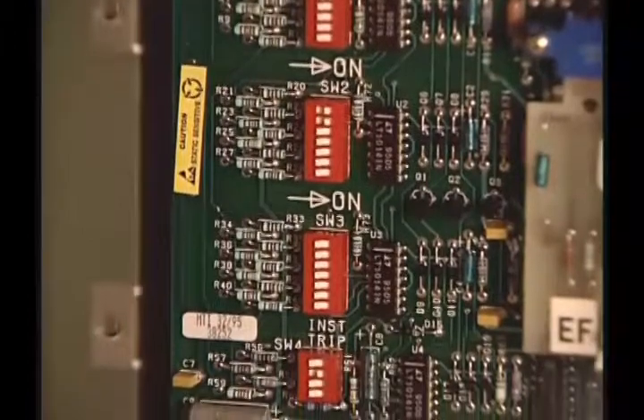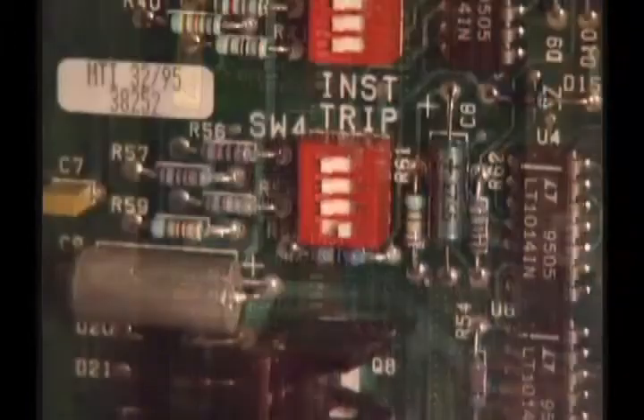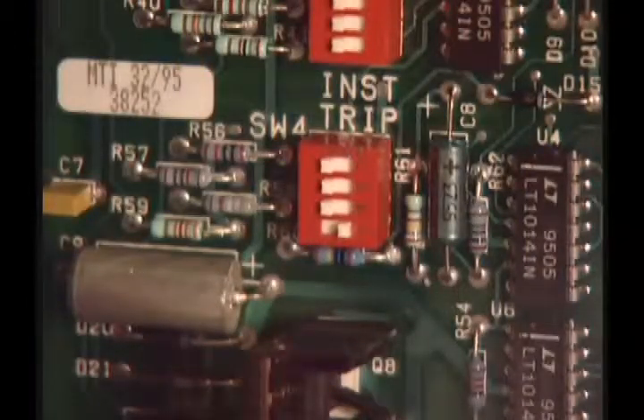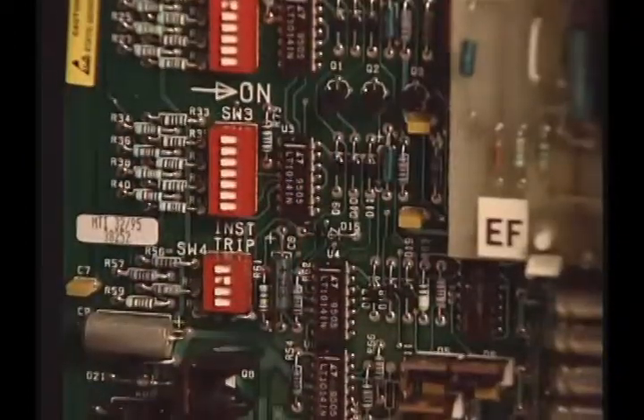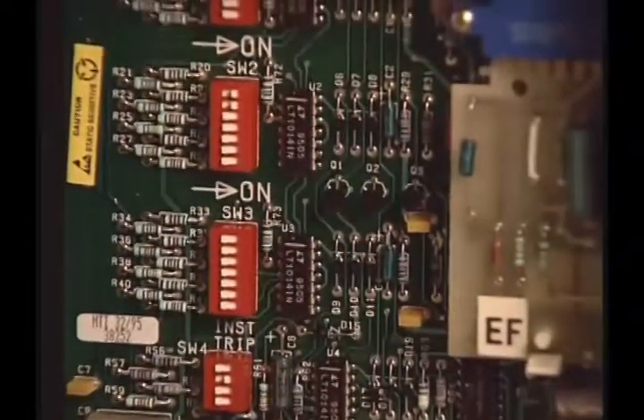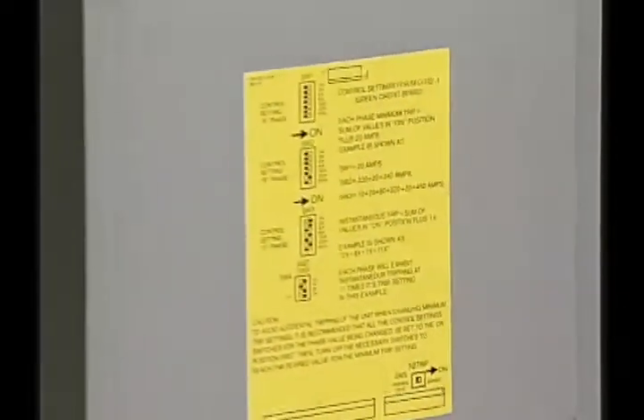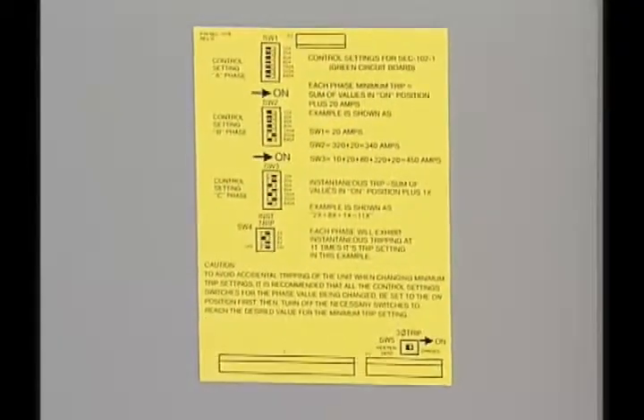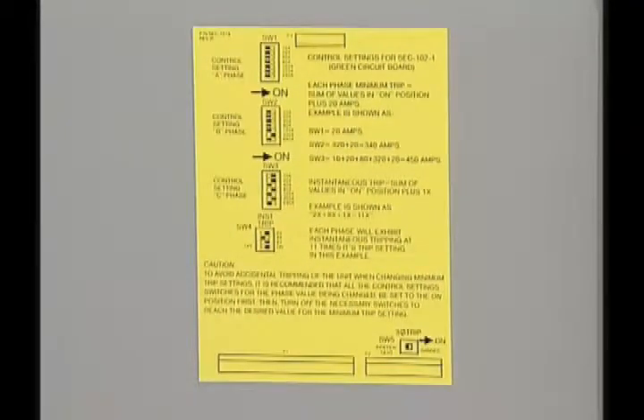Dip switches on the control circuit board set the minimum trip levels for each phase, activate and program instantaneous trip, and also allow selection of single-phase or three-phase trip. The control settings decal, located on the inside of the control housing cover, provides a reference for setting the control's minimum and instantaneous trip values.